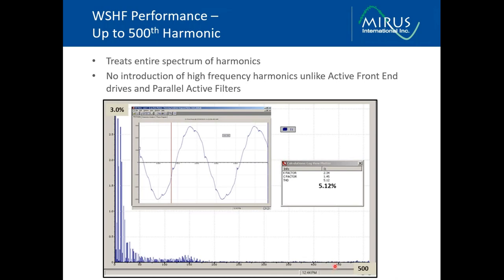So here we took some measurements with a meter that was capable of measuring all the way up to the 500th harmonic. On this scale, we're showing all the way up to the 500th harmonic. On the y-axis, we're showing the percent current harmonics. Maximum scale here is 3%. The 50th harmonic is here. So these are the harmonics that are in the system, all of them below 3%, and no introduction of high-frequency harmonics, which cannot be said for the active solutions.